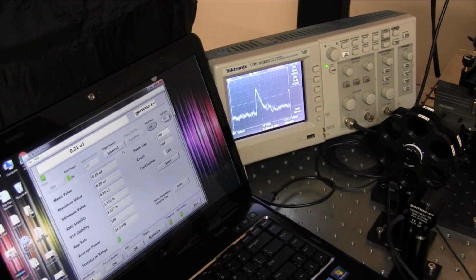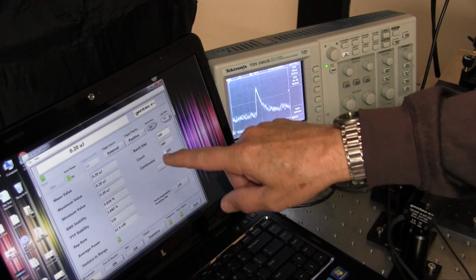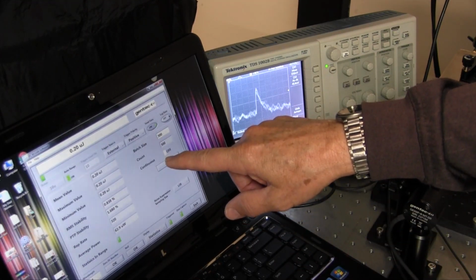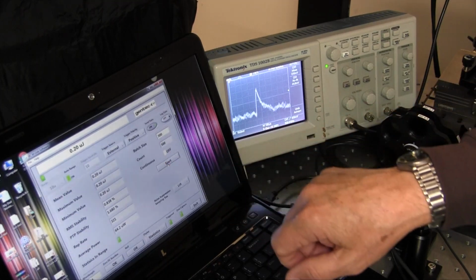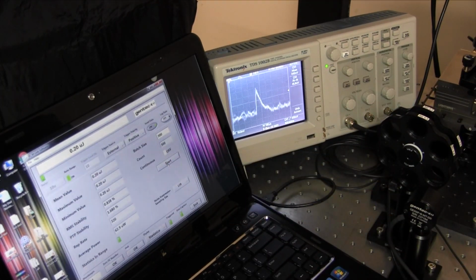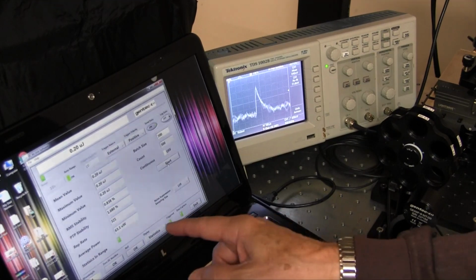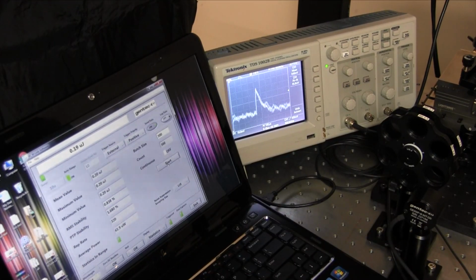Okay, now let's select the external trigger setting and take advantage of our noise suppression feature. I'll pick 128 pulses. I'll then start the data set, take a couple data sets, and you can see now we have a very stable 0.2 microjoules or 200 nanojoule reading with RMS stability of 0.838%, and the pulse rep rate, of course, is stable at 320 pulses per second with an external trigger.